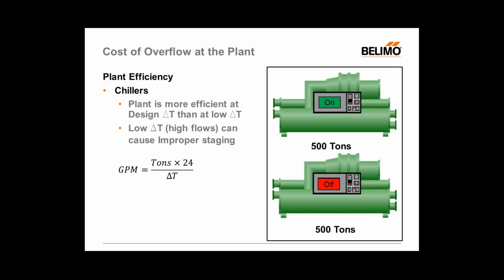If we take a look at the GPMs, we see here on the left that GPM, this is just a reformulation of the 500 times GPM times delta T, except we've changed from BTUH to tons of cooling. We have GPM equaling tons times 24 divided by delta T in degrees Fahrenheit. If we go ahead and say that this is a 12-degree chiller and that it requires 12 degrees of delta T, if I'm at design, 500 tons of cooling nets 1,000 gallons a minute.